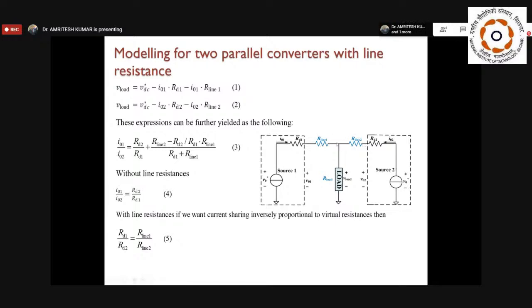then you simply put R line 1, R line 2 to be 0. So you will arrive at a simple equation. You can see here, without line resistance, the sharing of the current is inversely proportional to the droop resistance. So it means that if we suppose there is no line resistance and you are applying the droop, then based on the droop value, that is the virtual resistance, you can have this current sharing.